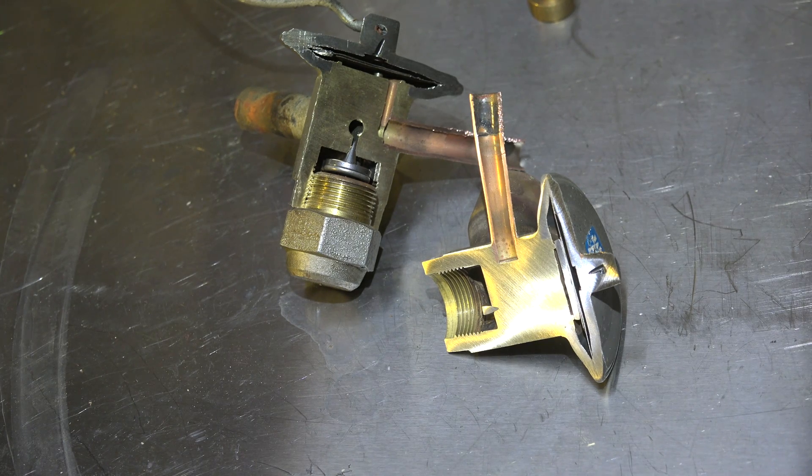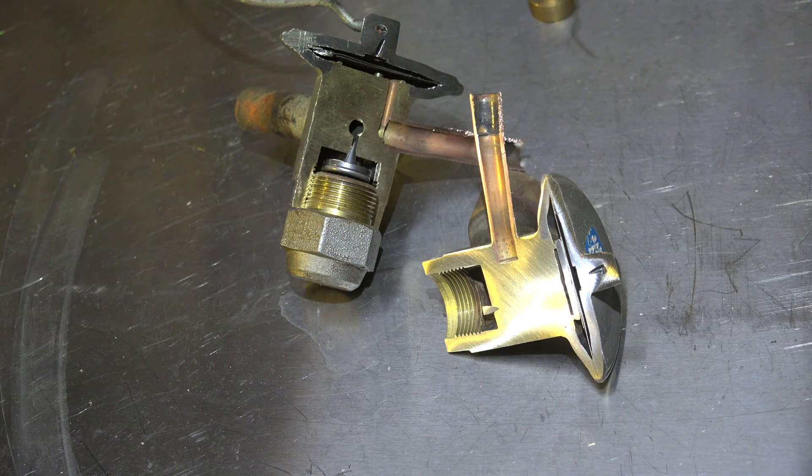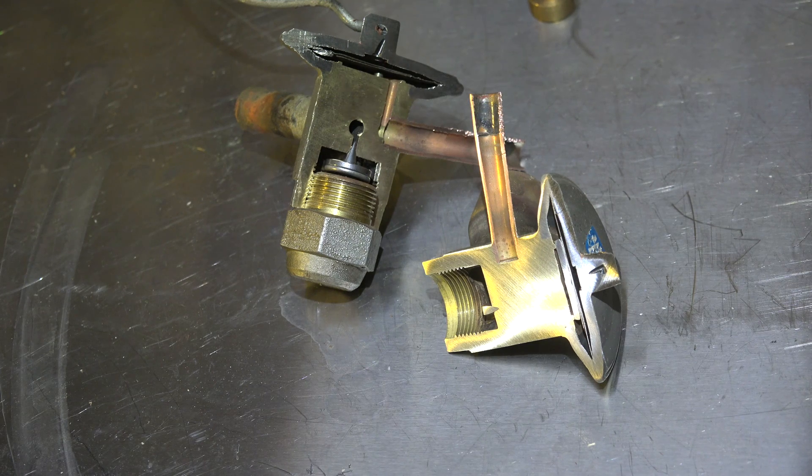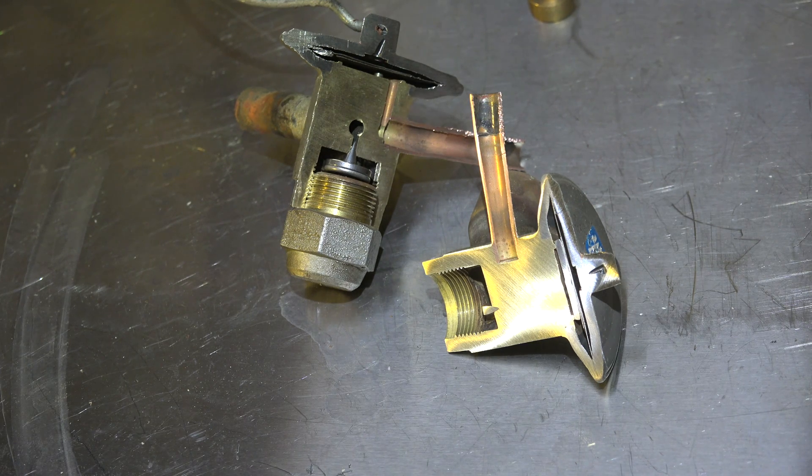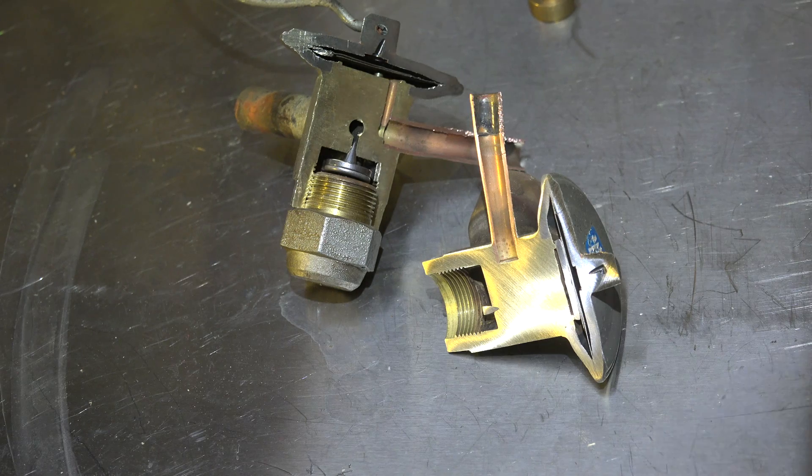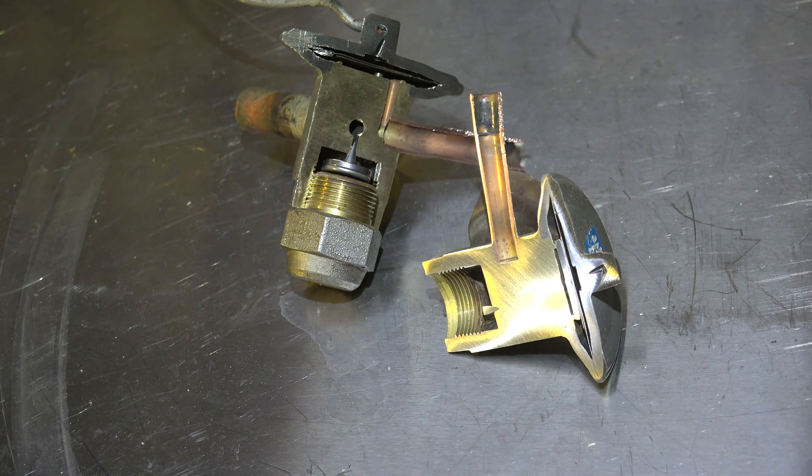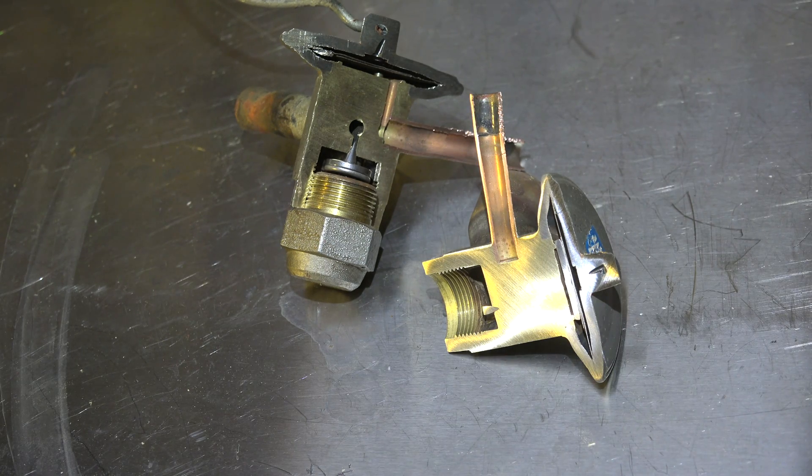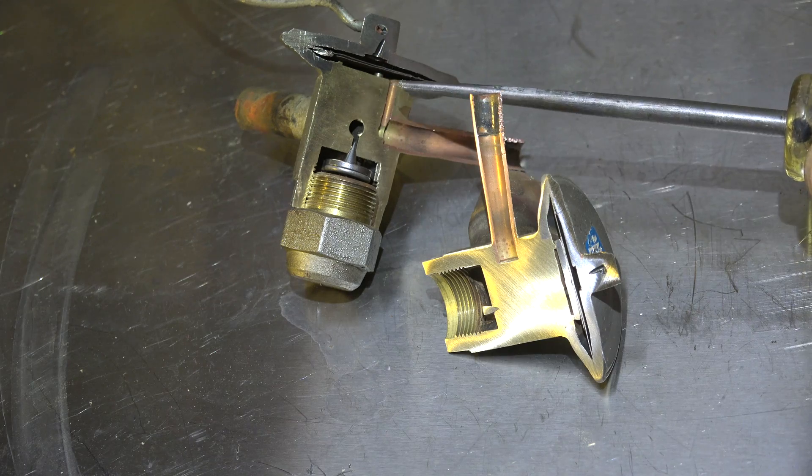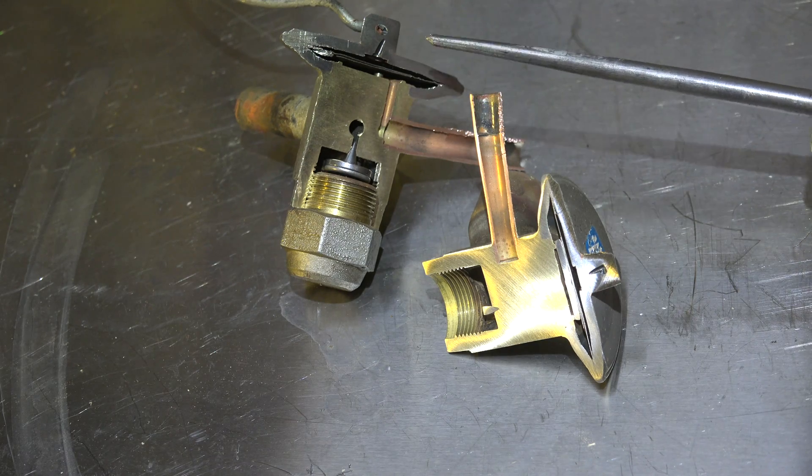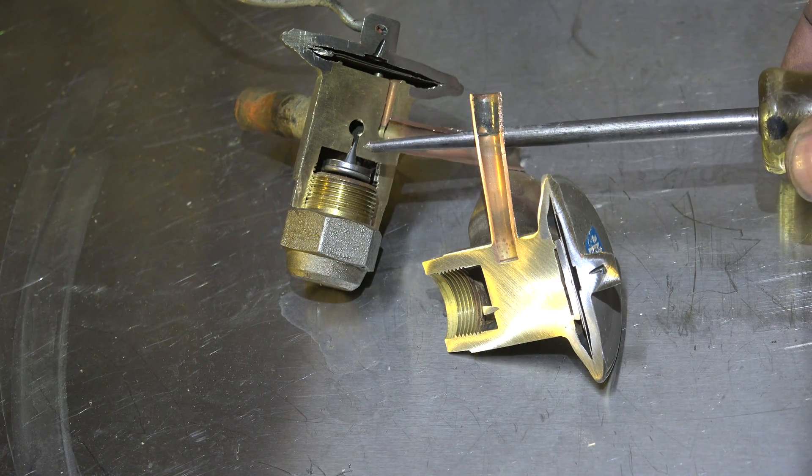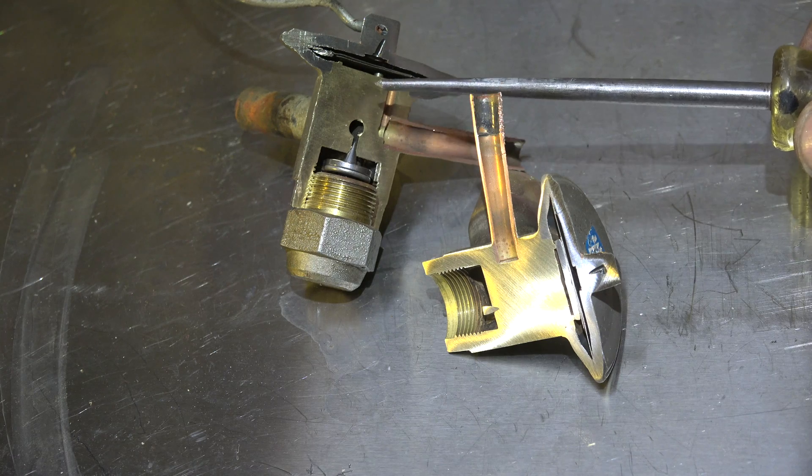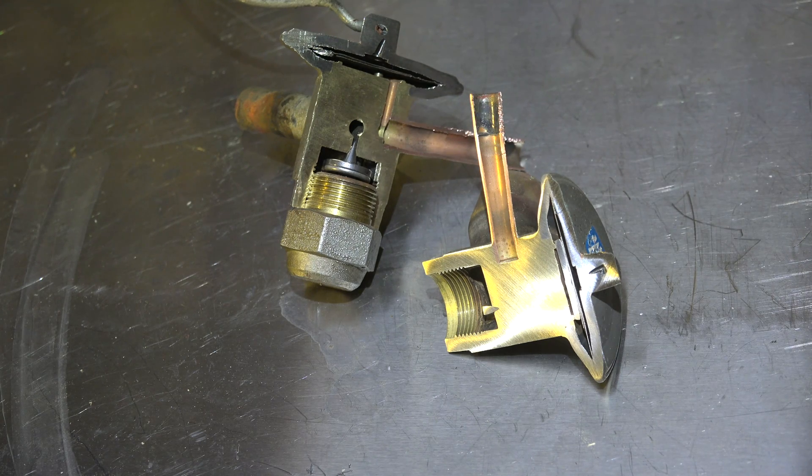Looking at this TXV, this is a non-bleed TXV. So what is a non-bleed TXV? What that means is when this thing shuts off, when the compressor shuts down, this needle valve closes completely. There is no connection through this valve between the high side and the low side on this valve when the unit shuts off.